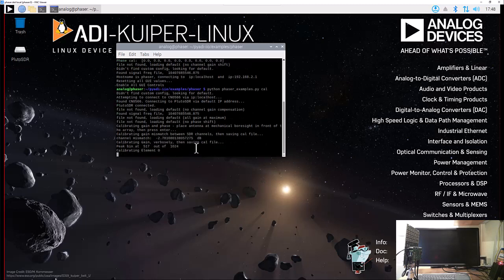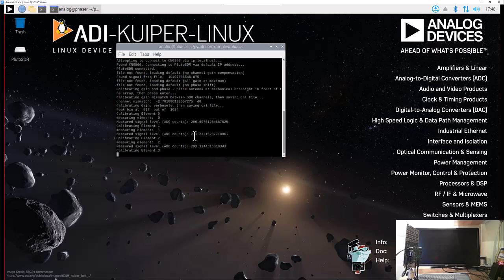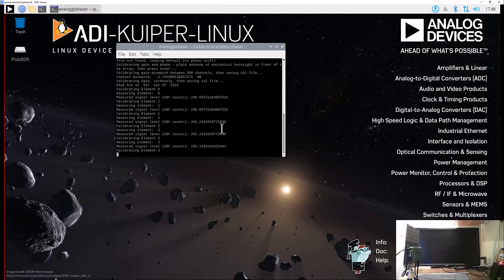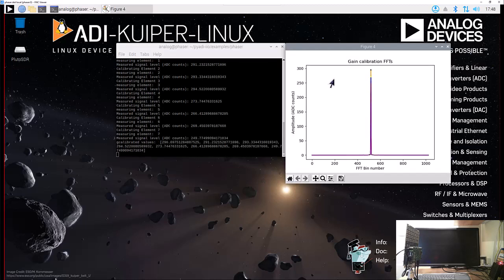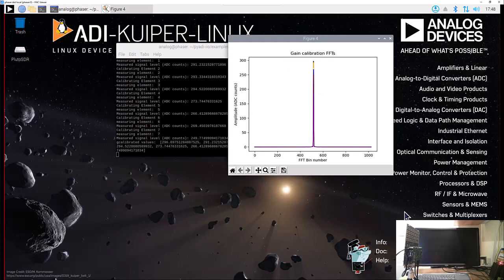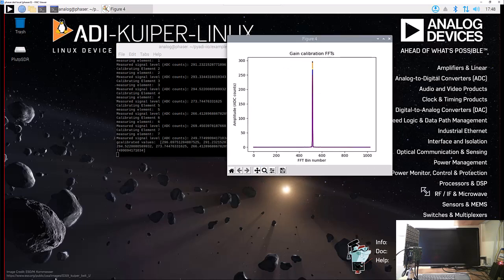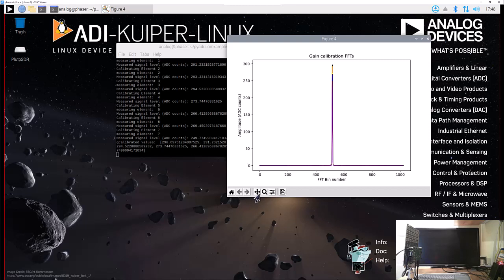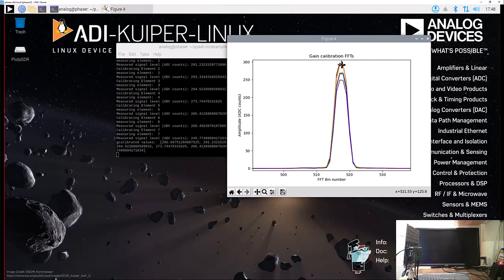So the first thing it's doing is calibrating. It runs a bunch of calibration routines to measure the difference between the 8 array elements. And we get some useful information here as well. With that single tone coming in, this is kind of interesting to look at. We can zoom in on the spikes, and we see that each channel has its own gain. We're going to measure this difference and compensate for it in the phaser software, or in the GUI.